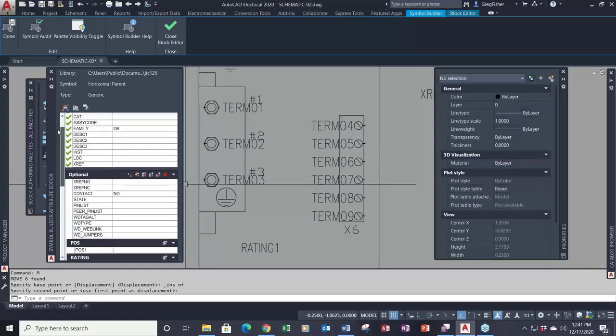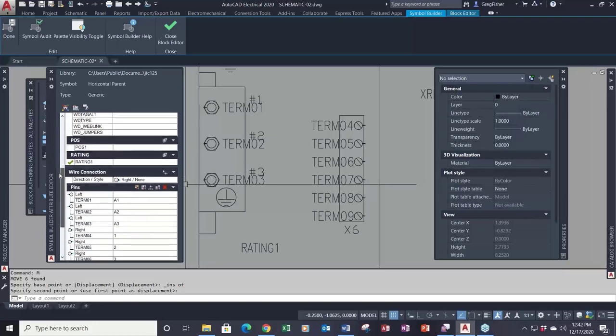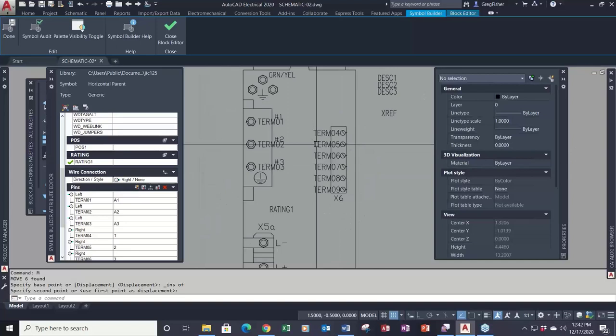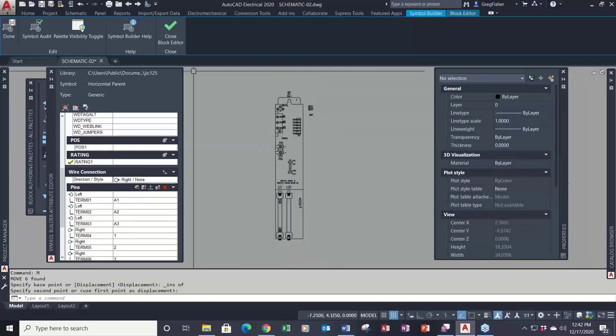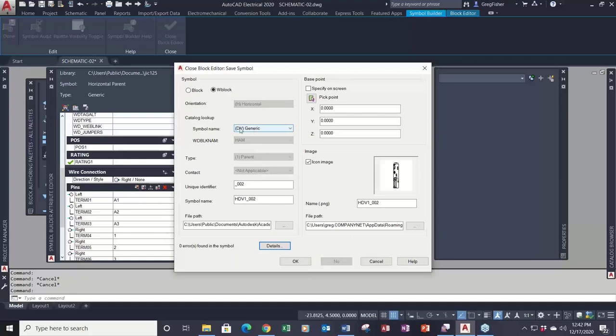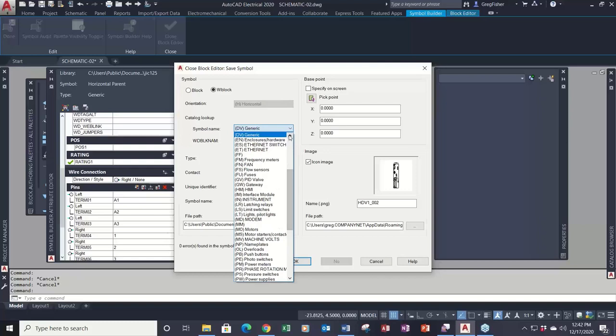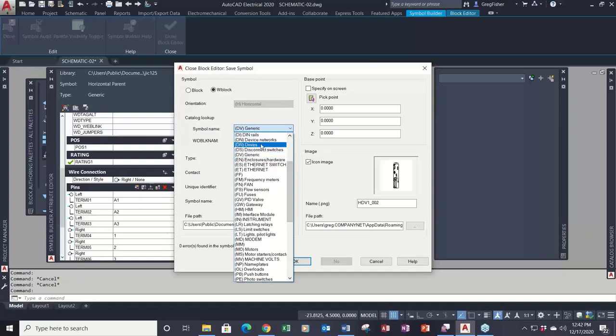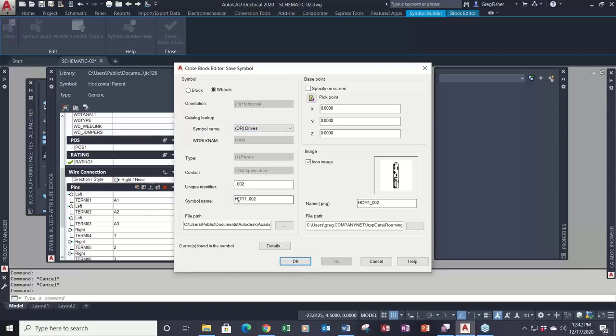At this point I'm done — those are all the attributes I want to use, not going to use any optional ones, and I have a rating in there. I'll pick 'Done.' Now, since I chose generic, the symbol name currently shows HDV1. I want the drive category, so I pick it from the list and notice it immediately changed the symbol name. This is why when you choose generic, you want to know ahead of time — I plugged in DR for the family code and DRV for the tag — and when you get to this dialog, make sure to select DR from the list of tables.